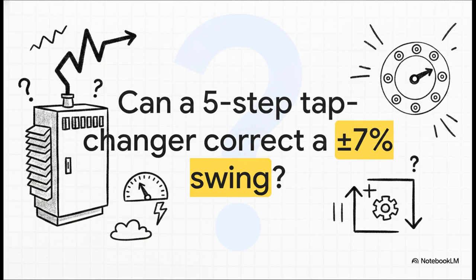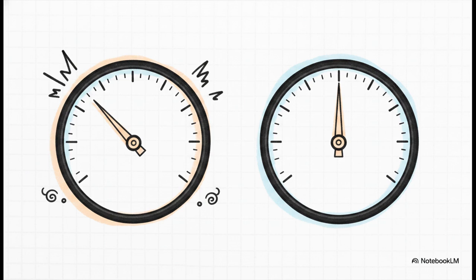So let's do a quick interactive check to tie all this mechanical stuff together. Imagine your incoming utility supply fluctuates by plus or minus 7%. And let's say you have a standard 5-step tap changer that adjusts exactly 2.5% per step. Here's the big question. Can you fully and reliably correct for that swing? Just take a second to do the math in your head. The answer is no, not really.